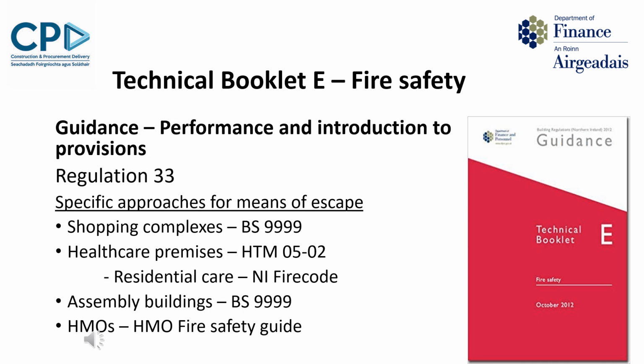Under the Guidance, Performance and Introduction to Provisions section, and the specific approaches for the design of means of escape given under Regulation 33, for shopping complexes, the relevant recommendations of BS 9999 is now cited rather than BS 5588 Part 10. For healthcare premises, HTM 05-02, which is Fire Code Guidance in Support of Functional Provisions, Fire Safety in the Design of Healthcare Premises, is referenced rather than the Northern Ireland Fire Code suite.